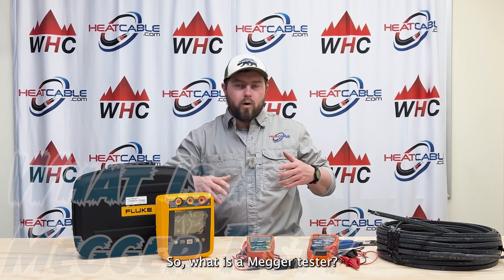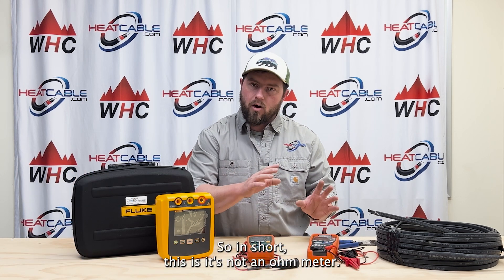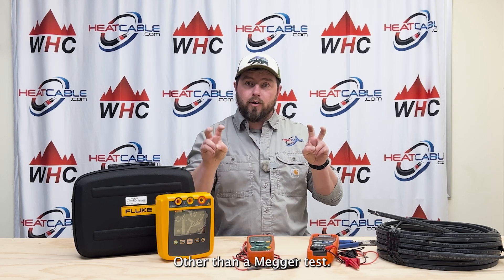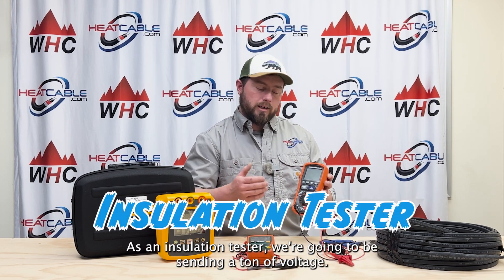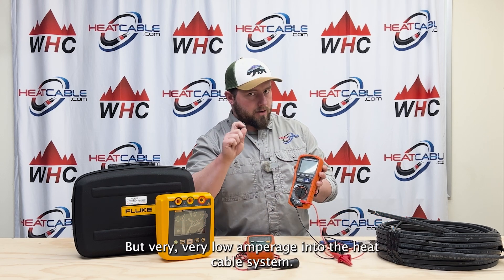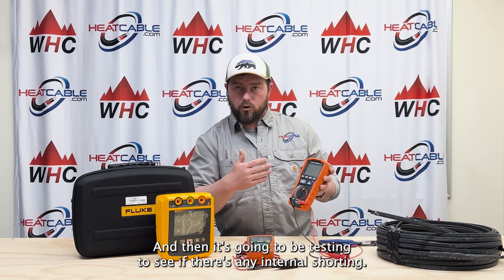So what is a Megger tester? In short, it's not an ohmmeter, it's not a multimeter — although it can do a couple of things beyond a Megger test — but one of these Megger meters is really there as an insulation tester. We're going to be sending a ton of voltage but very very low amperage into the heat cable system, and then it's going to be testing to see if there's any internal shorting.